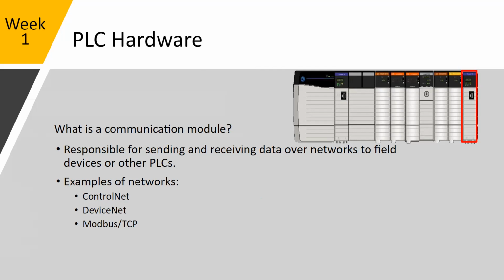Let's say you've got one PLC at one site that needs information from another PLC to know the level of a remote tank, and needs to know the flow at a remote site or a valve position at a remote site before it can open or close a valve. You would use these different field protocols. A lot of them are settling on an Ethernet based protocol just because it's widely available. But you will run into, especially with Allen Bradley, some of these proprietary ControlNet and DeviceNet protocols, and Modbus is literally everywhere. It's an old protocol. I think we do get into some of that in the programming course, but that's just the basics of COM modules. Are there any questions?